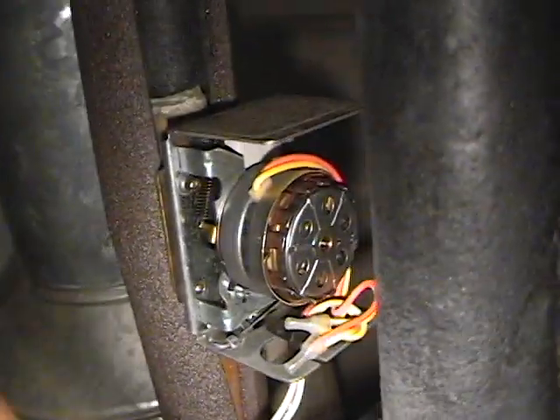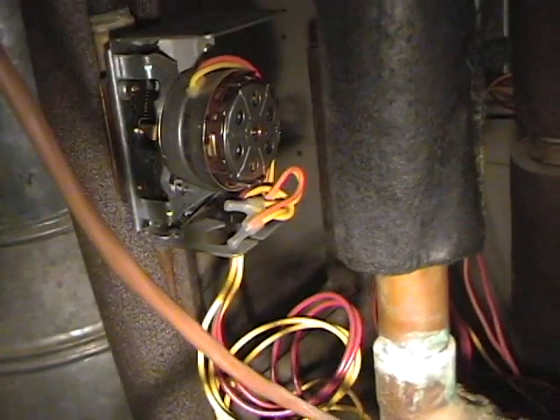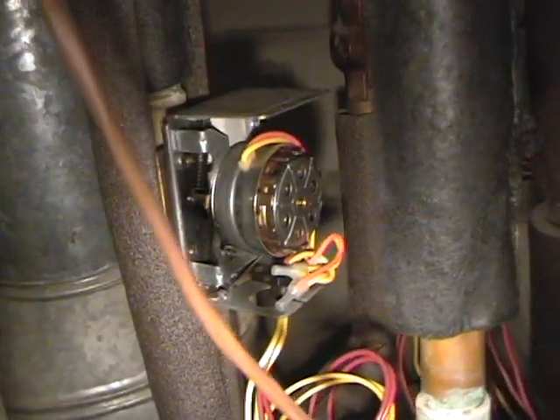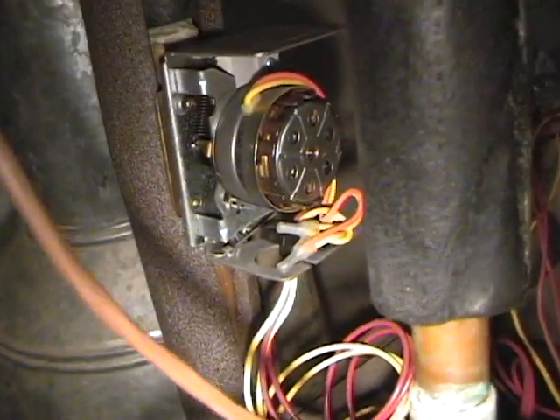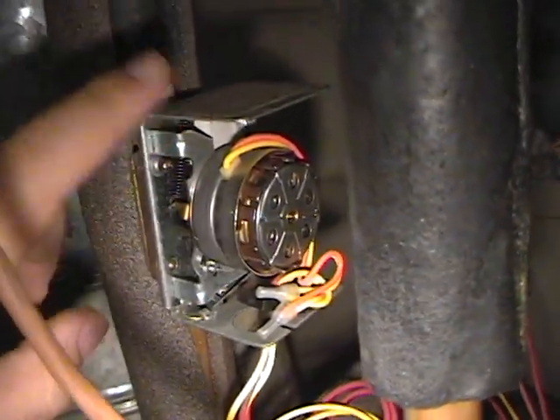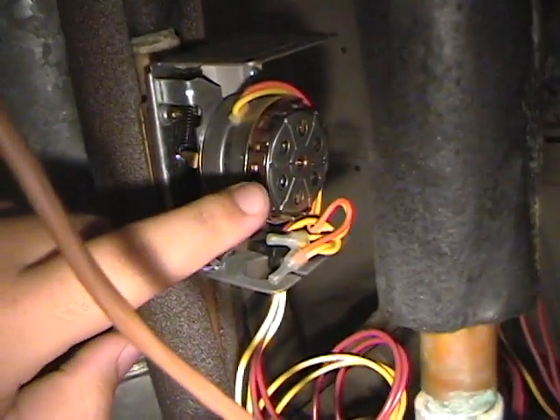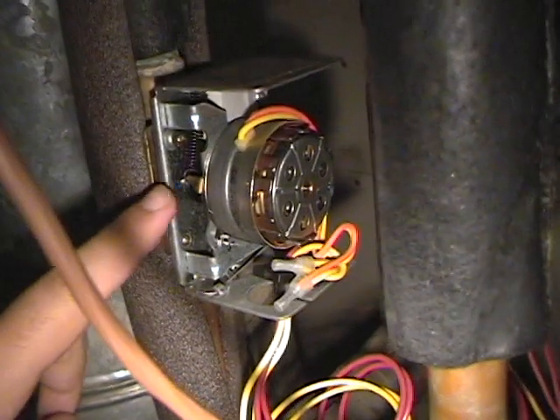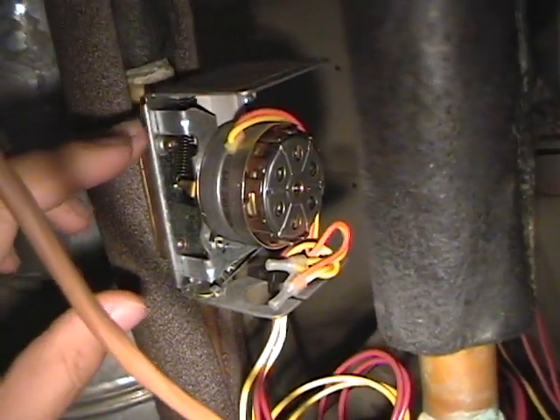And then basically what goes on is, once the temperature is satisfied on the thermostat, the power is obviously disconnected to the valve, which causes the springs to take over and force the valve closed, and at the same time disconnect power from the boiler.